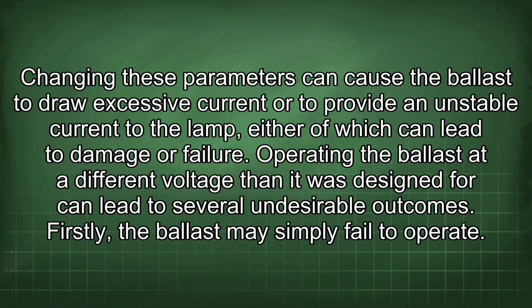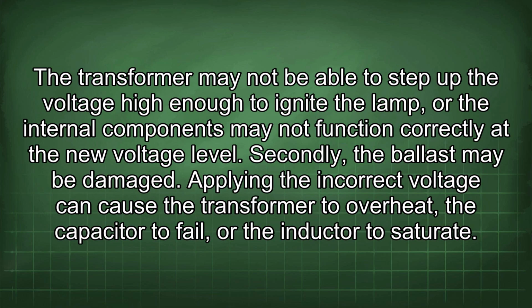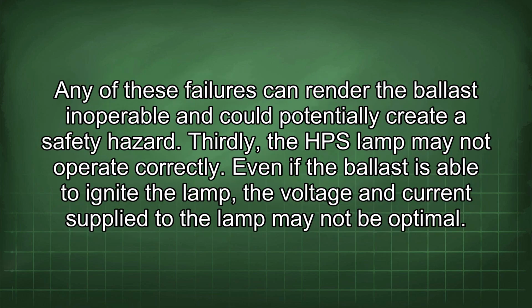Operating the ballast at a different voltage than it was designed for can lead to several undesirable outcomes. Firstly, the ballast may simply fail to operate. The transformer may not be able to step up the voltage high enough to ignite the lamp, or the internal components may not function correctly at the new voltage level. Secondly, the ballast may be damaged. Applying the incorrect voltage can cause the transformer to overheat, the capacitor to fail, or the inductor to saturate. Any of these failures can render the ballast inoperable and could potentially create a safety hazard.